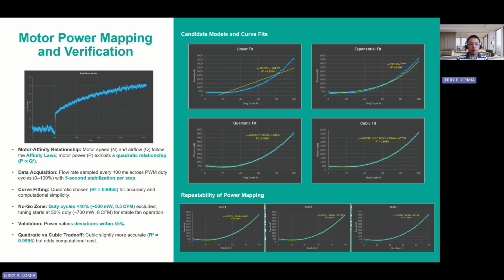What sets motor power mapping apart from the curve fitting done later in the study is that the mapping specifically described the power to airflow relationship based on empirical measurements across different PWM duty cycles. In contrast, curve fitting uses this mapped data of motor power and airflow rate to create a general predictive model that can be applied in real-time airflow tuning without requiring continuous measurement from external sensors.